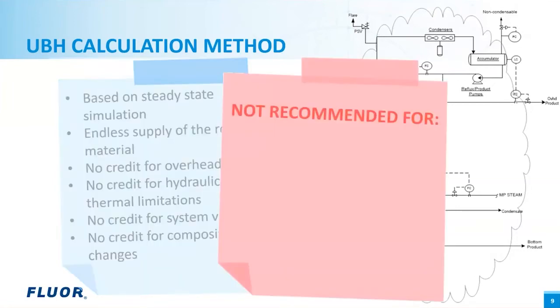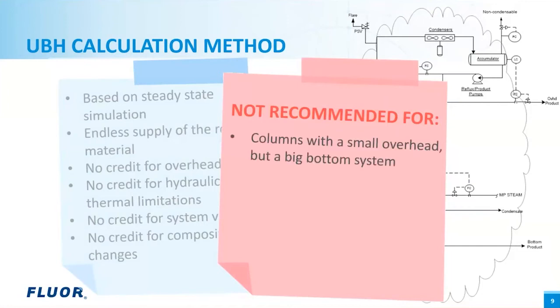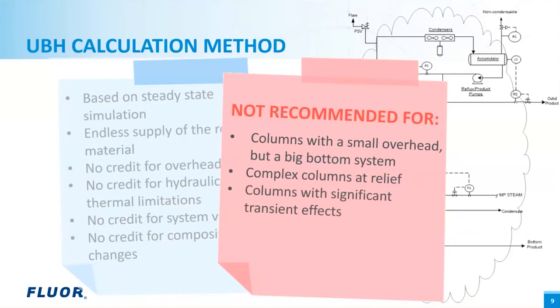The unbalanced heat method is usually used for grassroots projects. However, it is not recommended for columns with a low overhead-to-bottom flow ratio — meaning a small overhead and large bottom system, such as a stripper or stabilizer. It is not recommended for complex column systems, for example reactive distillation columns or columns with relief near critical regions. It is also not recommended for columns with significant compositional changes and transitional changes during relief. The vapor blowthrough case cannot be handled by the unbalanced heat method either.